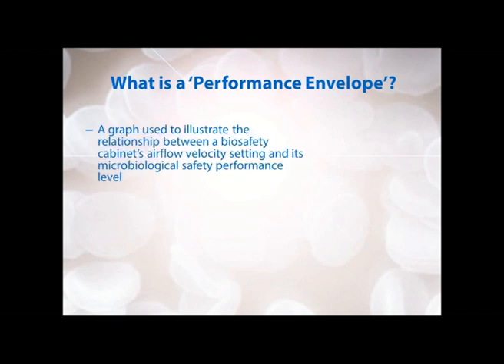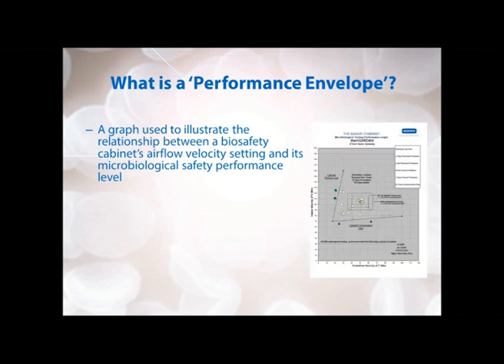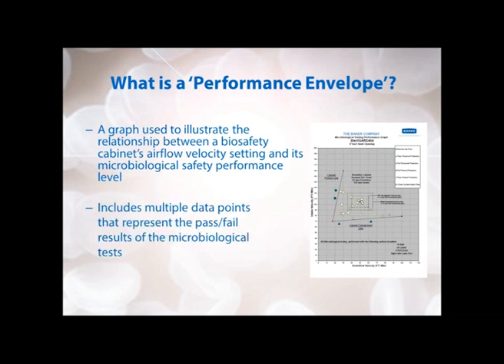So first, what is a performance envelope? The performance envelope is a graph that is used to illustrate the relationship between a biosafety cabinet's airflow velocity setting and its microbiological safety performance level. It includes multiple data points that represent the pass or fail result of the microbiological testing. There's also a series of lines that define the limits or boundaries based on these testing results. We'll get into more details in just a minute.